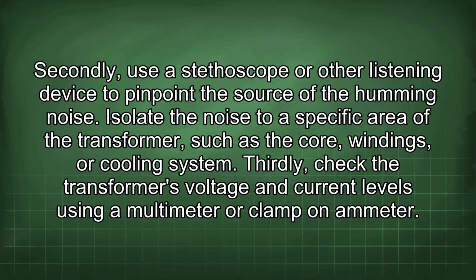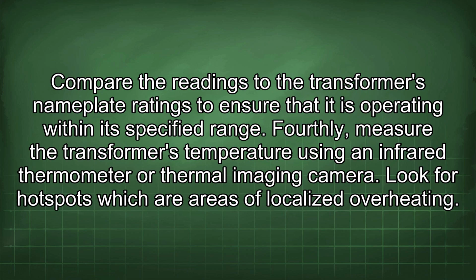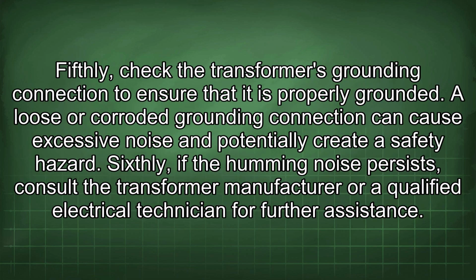Thirdly, check the transformer's voltage and current levels using a multimeter or clamp-on ammeter. Compare the readings to the transformer's nameplate ratings to ensure that it is operating within its specified range. Fourthly, measure the transformer's temperature using an infrared thermometer or thermal imaging camera. Look for hotspots, which are areas of localized overheating. Fifthly, check the transformer's grounding connection to ensure that it is properly grounded. A loose or corroded grounding connection can cause excessive noise and potentially create a safety hazard.